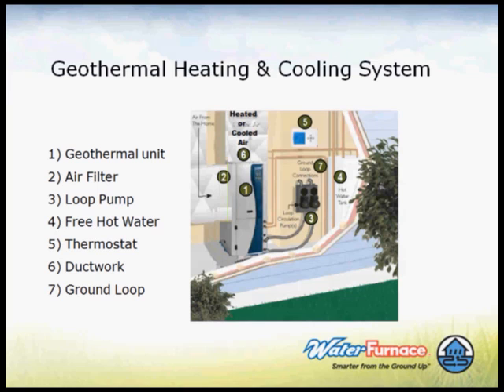You have the free hot water, number 4. We normally plumb into this—you don't have to do it, but it's an advantage if you can. We can plumb into an electric water heater and supply about half of your hot water energy over a year's time. I'll see anywhere from 47% to 52% on the reports we put out. That's a byproduct of compressor heat that otherwise we'd just have to dissipate off somewhere. So when your system is working hardest in the summer on really hot days, we're supplying hot water for you, and when the compressor's working hardest in the winter, we're supplying hot water for you then too.